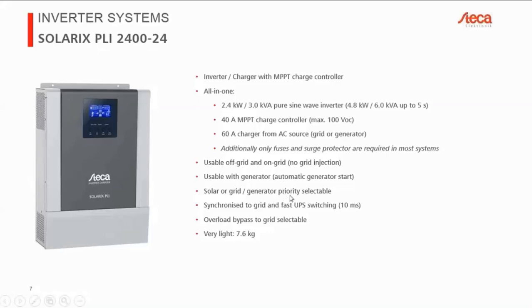Then, as I said, the priority is selectable between solar or AC source. We are always synchronized to the grid, so as soon as there's a valid signal on the AC input connector, so as soon as there's a valid sine wave, basically, the inverter will automatically synchronize to that sine wave, so that if it needs to switch over, then it's already synchronized beforehand, so we can switch over very, very quickly in 10 milliseconds. So that's basically 1/2 wave.